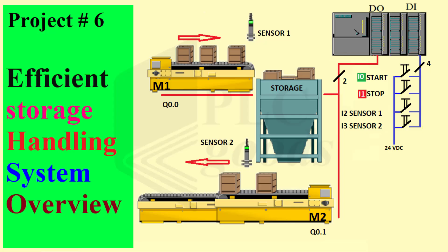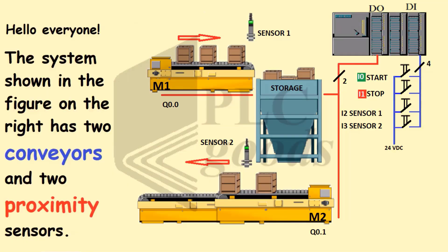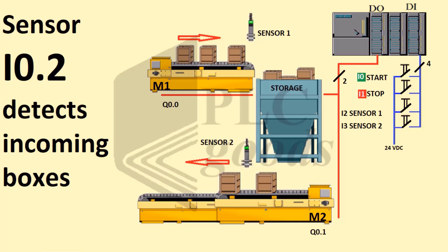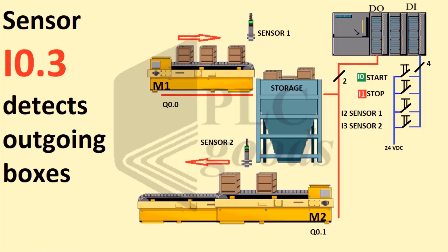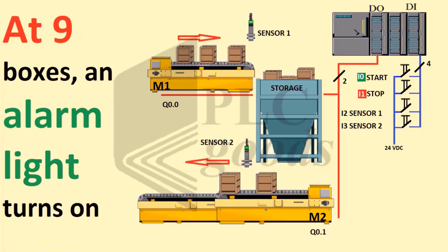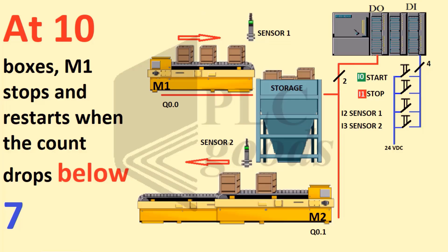Project number six: efficient storage handling system overview. The system has two conveyors and two proximity sensors. When the start button is pressed, M1 and M2 move boxes in and out of storage. Sensor I2 detects incoming boxes, sensor I3 detects outgoing boxes. The content of MW10 tracks the box count. When the count reaches nine, an alarm light turns on, and when it reaches ten, M1 stops.